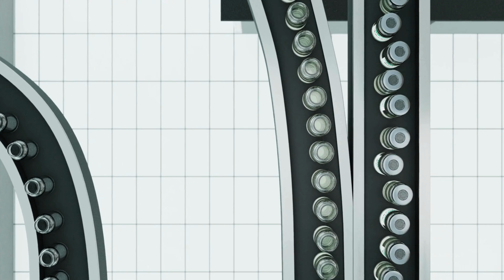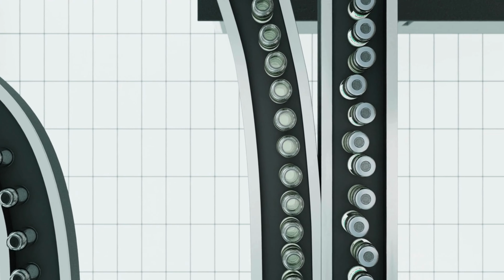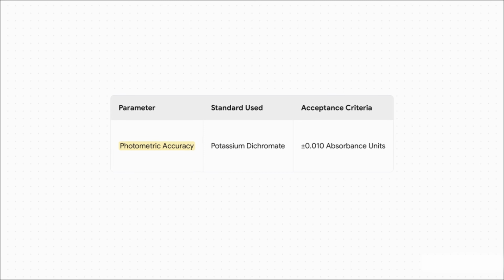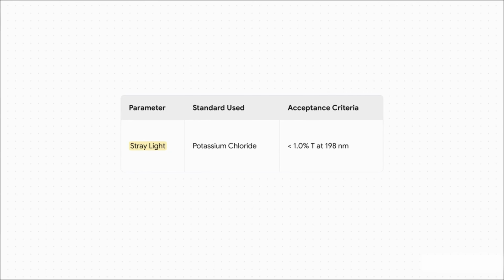Next, we've got photometric accuracy. Here, using a different standard, we're checking if the instrument is measuring the amount of light correctly. This tells us how much of a drug is in our sample. It's not enough to see the right color, you have to measure its intensity perfectly. And the margin for error here is just 1/100th of an absorbance unit. Tiny.